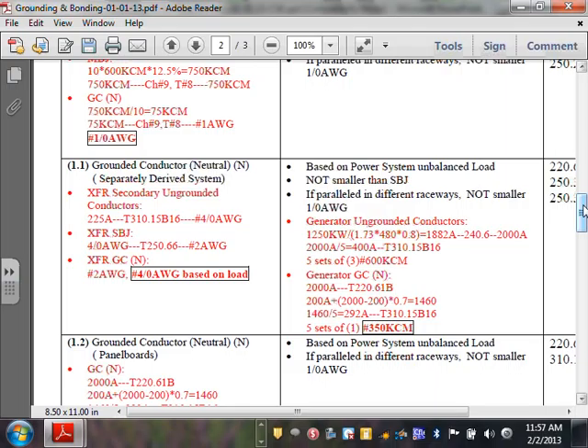So you size the grounding conductor. You guys typically take the full load. Here's my full load amp. Well, it depends. You multiply by 1.15 if your circuit breaker is not at the generator. If your circuit breaker is not right at the generator, you multiply by 1.15 when you size conductors. So I went from this size directly into my overcurrent protection device, which is going to be the next size here, 2000. Divide it by 5, and I came up with 5 sets of 600 kcmil.